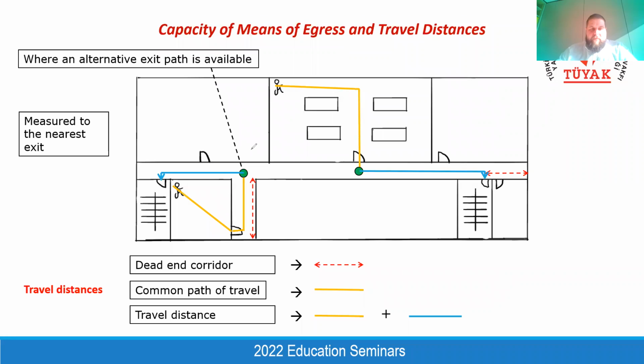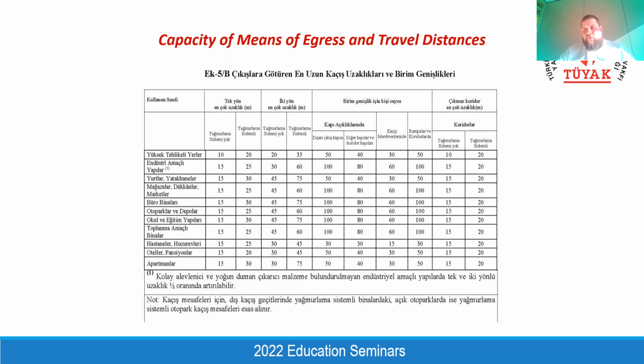For example, if you don't have a sprinkler system, you probably need to provide a third staircase in the middle of your building to fulfill the travel distance requirement of the Turkish Fire Code. Instead of providing additional staircases or making some structural and architectural revisions, you are allowed to provide a sprinkler system and execute your design accordingly. Most architects prefer it because revising the structural and architectural design according to the non-sprinkler building requirements is generally more expensive and harder than providing a sprinkler system. That's why you need to know that, and keep it in your pocket as a second alternative.